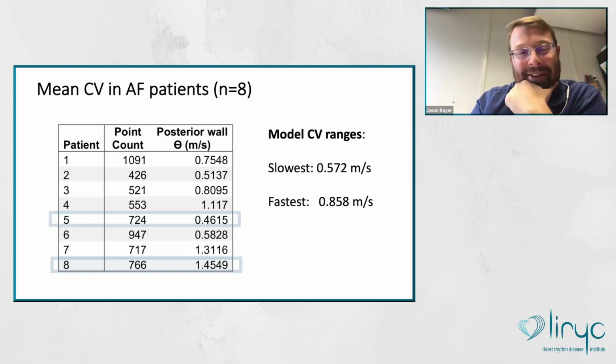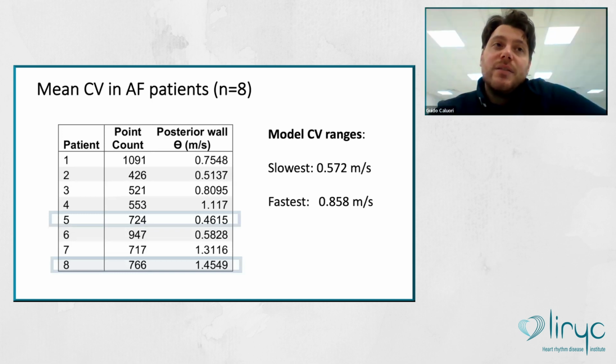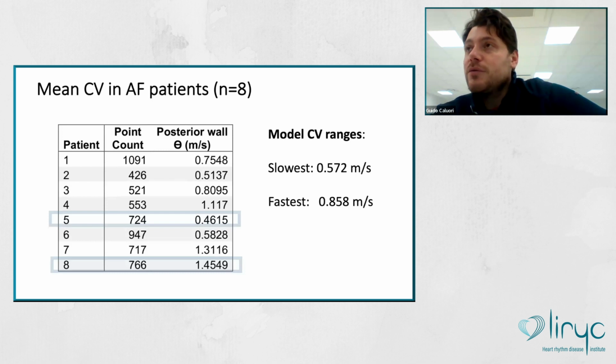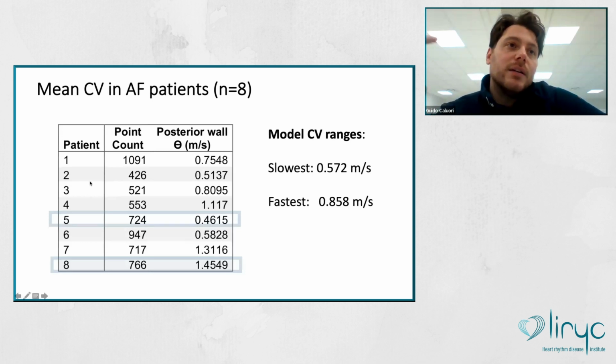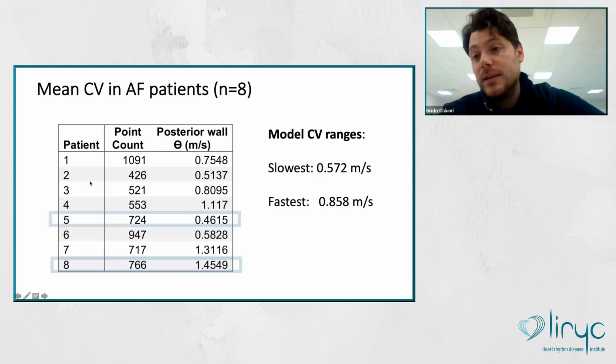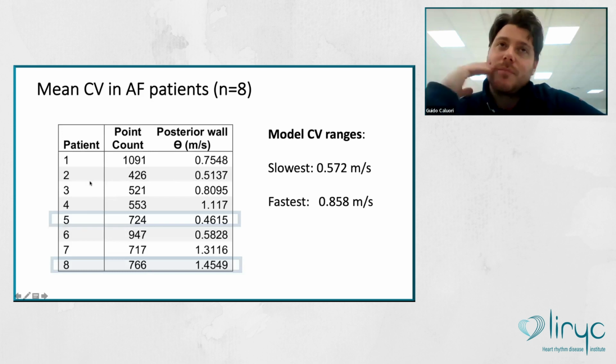You are correct. But I can tell you from experience, if you're looking at automatic annotation and resolution, the Rhythmia system is the best. If you're looking at versatility in terms of algorithms or annotations, probably the Carto system, and the Insight also is quite okay.